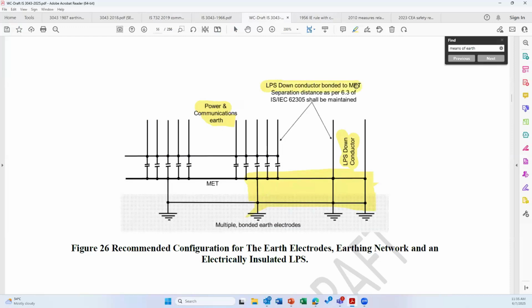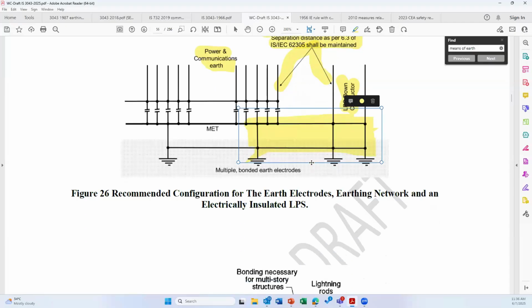In such a case, with the LPS down conductor bonded to MET, the separation distance as per 6.3 of IEC 62305 shall be maintained. So you should keep the separation distance, meaning the lightning protection shall be physically away from the building or other earthed metal parts of the building. So these are some of the changes which have happened.